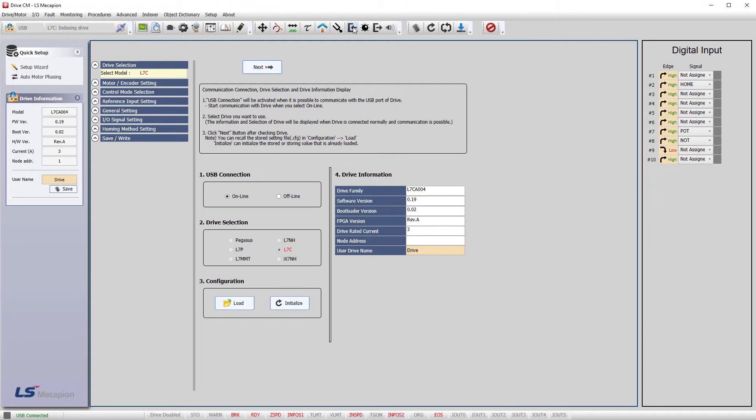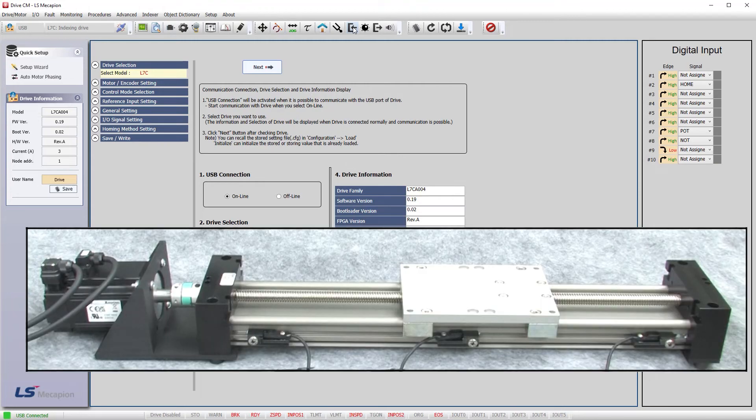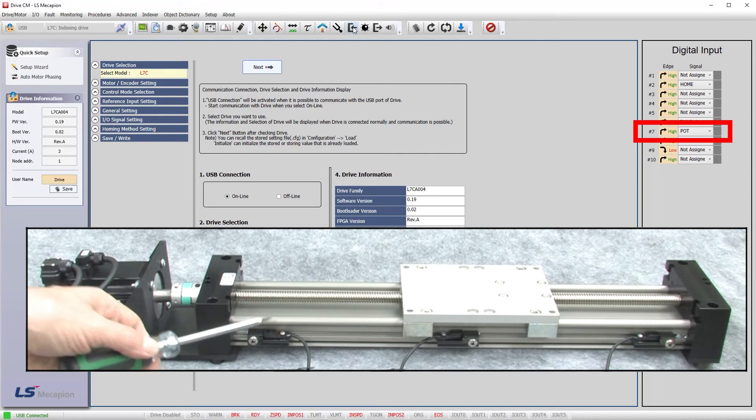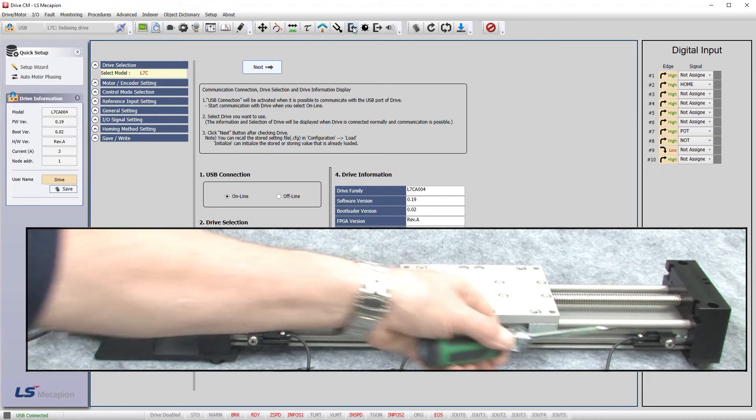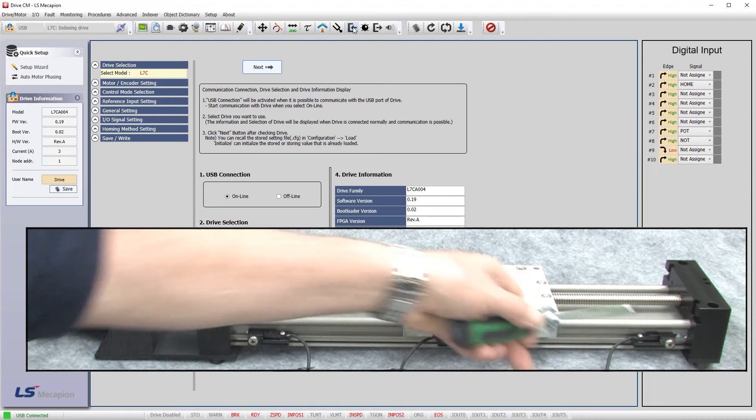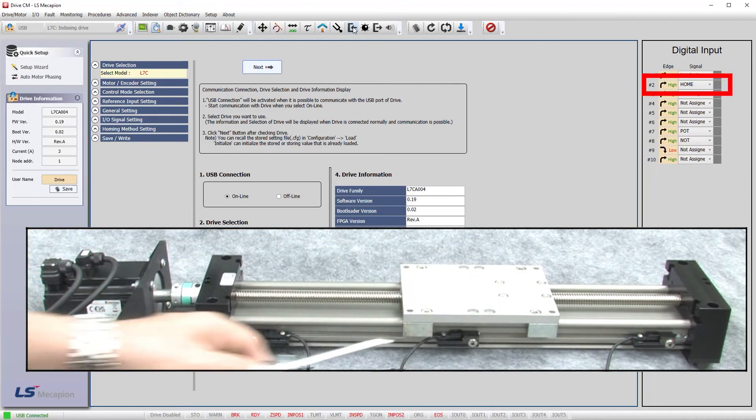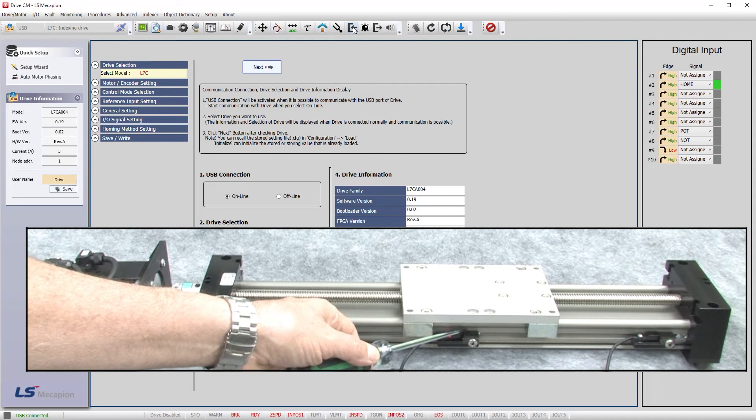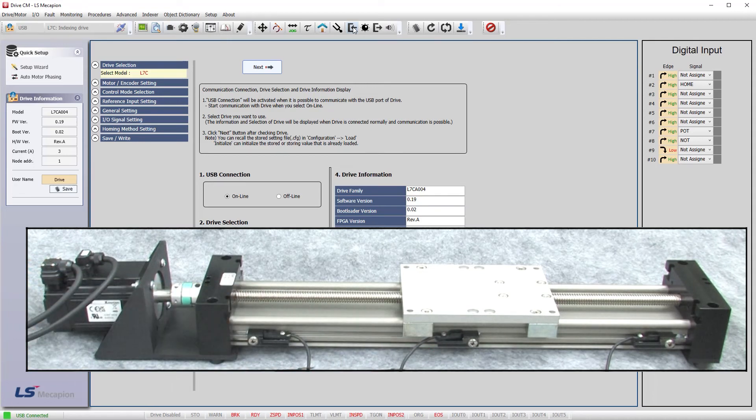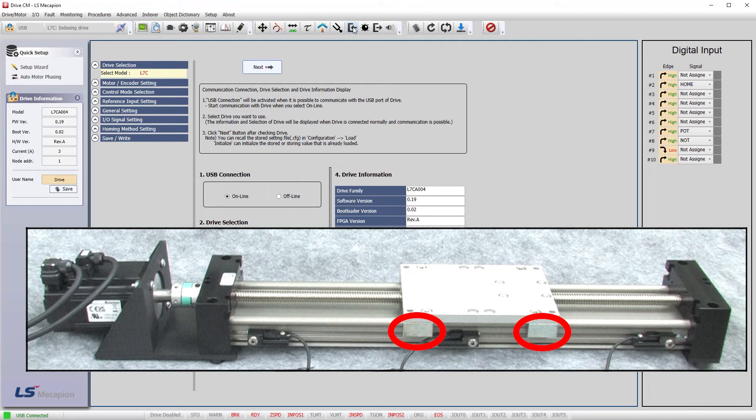If I hold a screwdriver over what I think the positive limit should be, yep, the positive limit lit up. Negative limit? Yep. Home sensor. Perfect. This carriage has two detection points which are also called flags or pawls or tags. Which means the home position will change depending on what we are doing and which of these hits the sensor first.